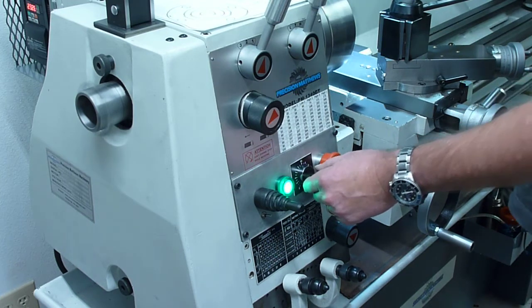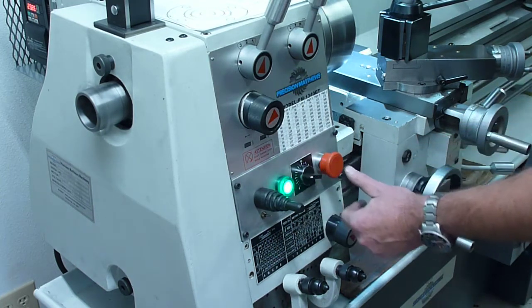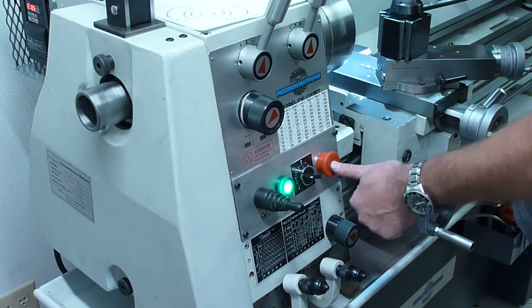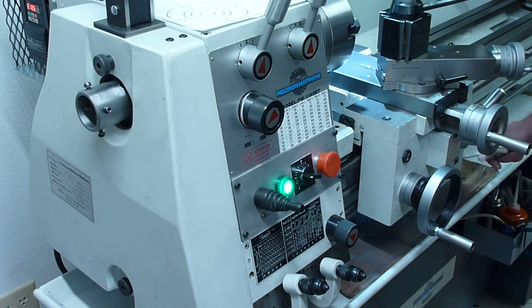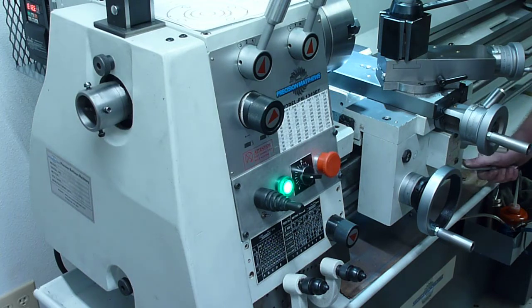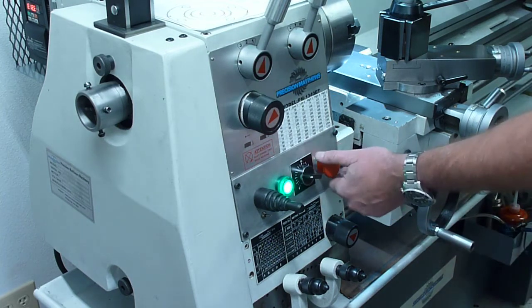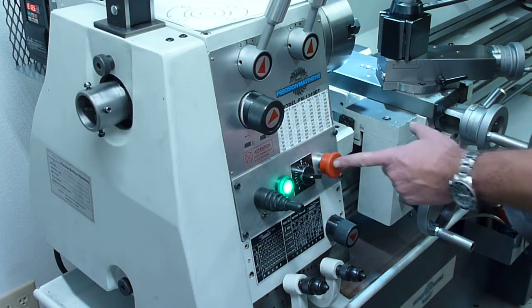If you have to stop the lathe in an emergency situation, obviously you hit the emergency stop button. The lathe should stop. However, you should be able to move the motor control switch to forward or reverse and the lathe should not start. Come over and reset the emergency stop button.